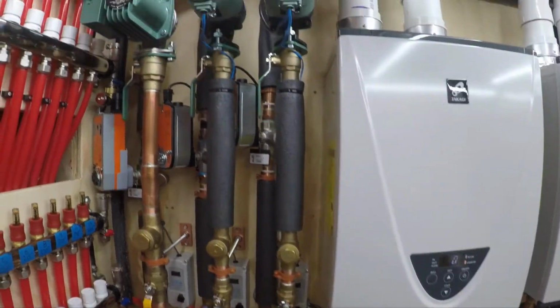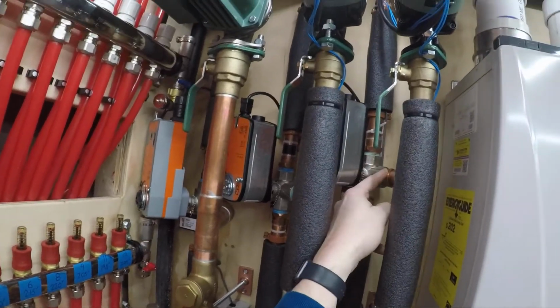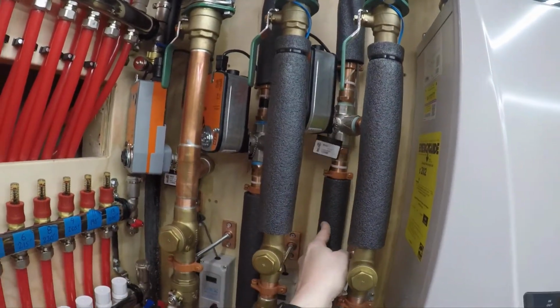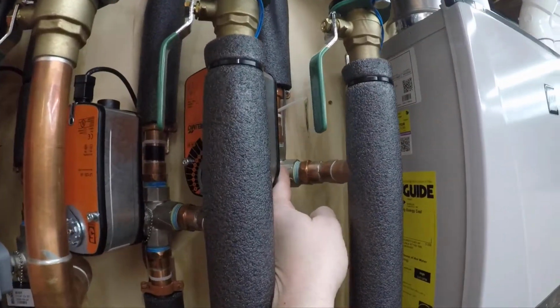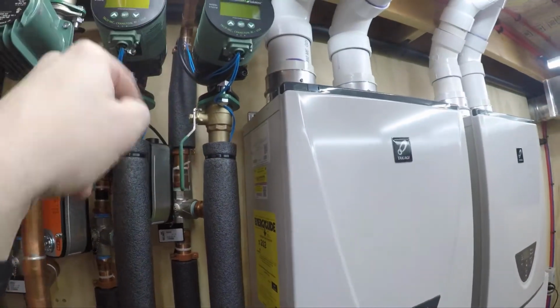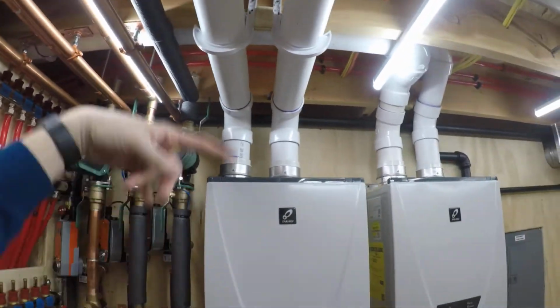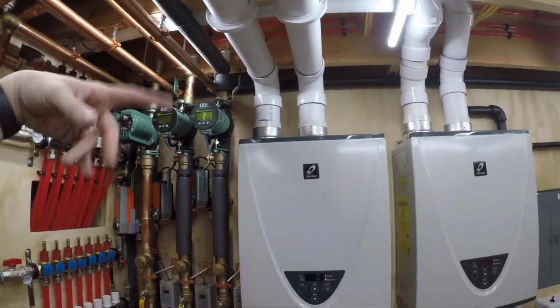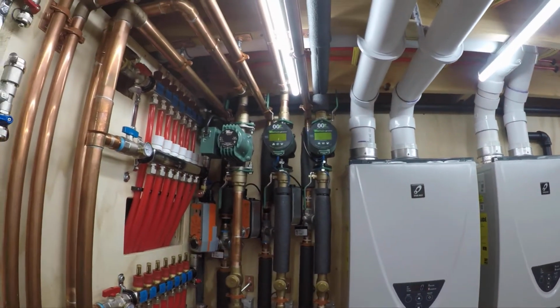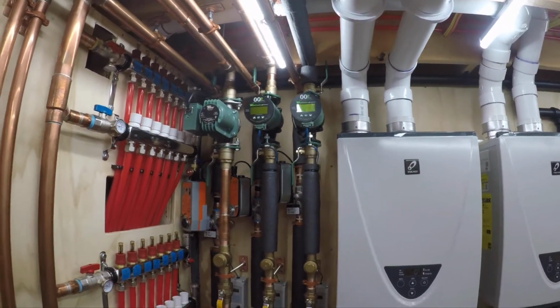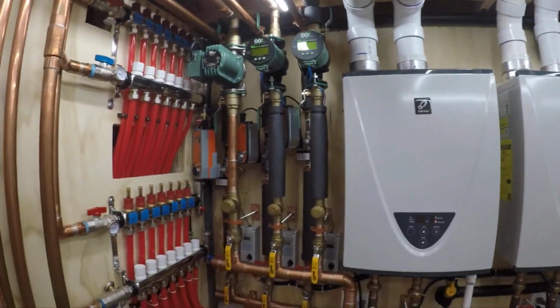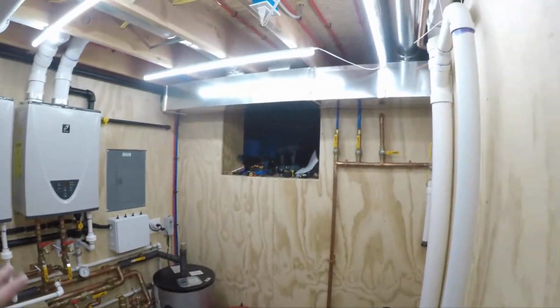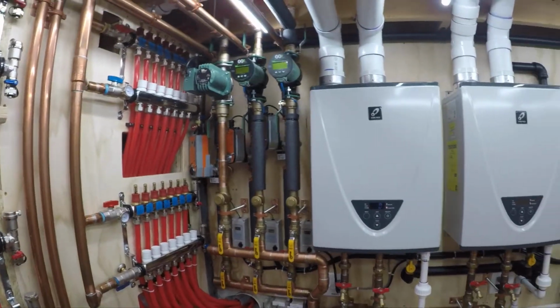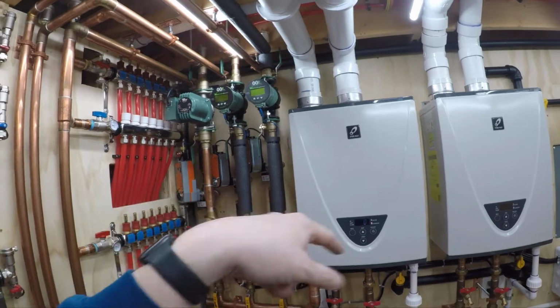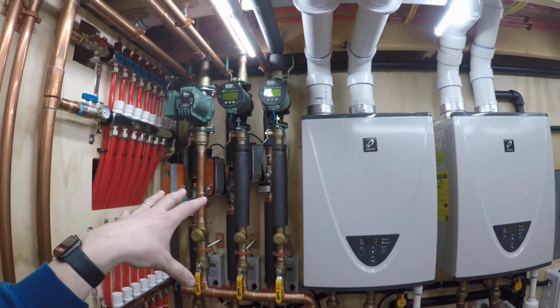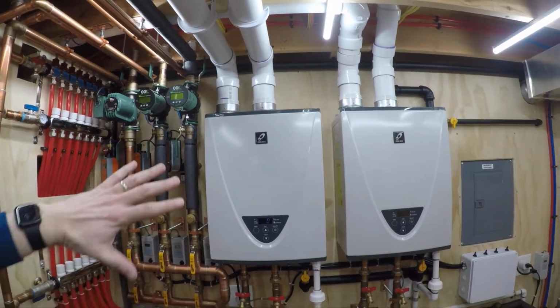The aquastat turns off. It closes this three-way valve so that now, instead of the glycol going back to get more heat, the glycol bypasses and comes back into this loop. And because these are on all the time, it just keeps pumping and pumping and pumping through the floors. And that's called continuous circulation. And what it does is it really evens out the heat. You don't get hot spots, you don't get cold spots, especially in the slabs, like the basement and the garage. If there's areas that you might be a little bit light on PEX, or it's at the end of your serpentine, if you did a serpentine pattern, you know, towards the end, it can get a little cooler. It really evens all that heat out.